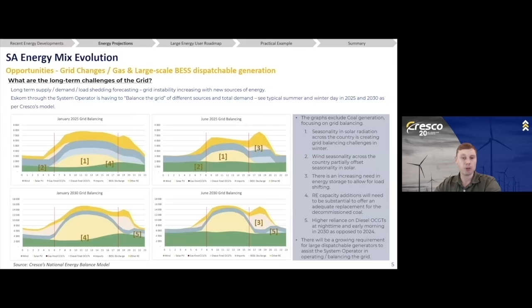But by 2030, Cresco modeling shows materially more BESS in the system. But importantly, BESS is now not just supporting evening peaks, it's also increasingly required in the early morning hours to provide grid stability. So what's changing is not just the size of the peaks, but the duration of stress on the grid. And short duration BESS is effective for evening peaks, but as gas availability remains uncertain and coal continues to decline in the grid, longer duration BESS becomes critical to support both early mornings and extended peak periods. So in other words, BESS starts to move from just peak shaving into system adequacy.